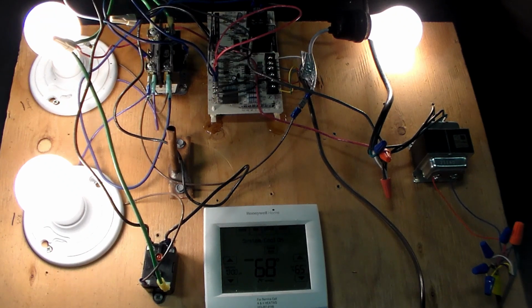It's basically when it reads closed, which should be really low ohms, the board knows it's frozen, which is usually below around 25 degrees, and that's coil temp, not outdoor temp. And when the defrost sensor reads really high ohms or open, depending on the kind of sensor it is, that tells the board that it's over 55 degree coil temp. So typically, the board reads it as closed with a 25 degree coil, and open with a 55 degree coil.